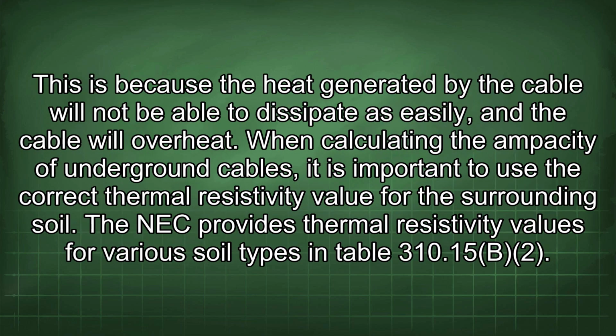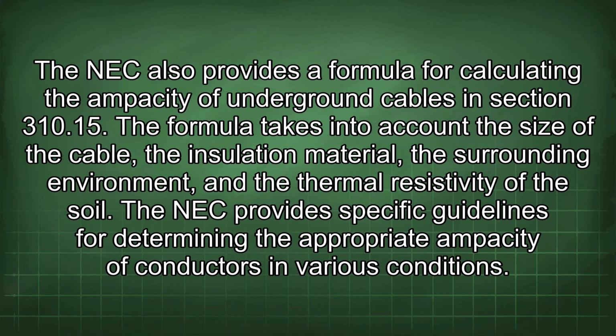This is because the heat generated by the cable will not be able to dissipate as easily, and the cable will overheat. When calculating the ampacity of underground cables, it is important to use the correct thermal resistivity value for the surrounding soil. The NEC provides thermal resistivity values for various soil types in Table 310.15(B)(2). The NEC also provides a formula for calculating the ampacity of underground cables in Section 310.15.